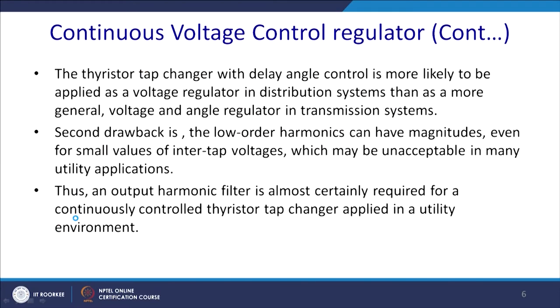The thyristor tap changer with delay angle control is more likely to be applied as a voltage regulator in a distribution system than as a more general voltage and angle regulator in a transmission system. The second drawback is that the lower order harmonics have quite a sufficient magnitude. We have seen the harmonic spectrum in our previous discussions. Lower order harmonics can have a significant magnitude even at small values of intertap voltages, which may be unacceptable in many utility applications. So, for this reason, we have to get rid of these disturbances. Thus, we have to find a solution.